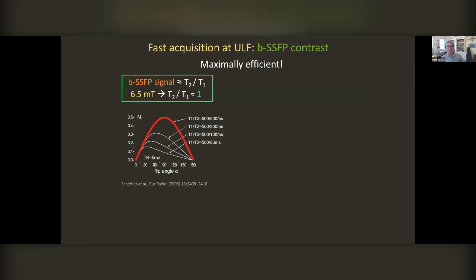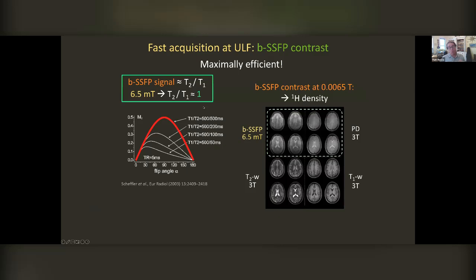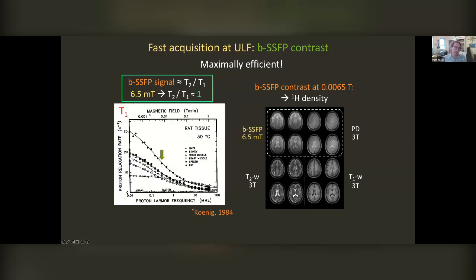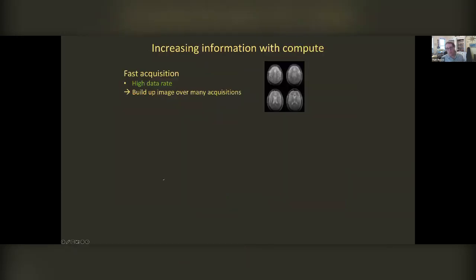Okay, so SSFP, it's maximally efficient at low field. The signal goes like T2 over T1. At our ultra low field, that ratio is unity. And so, we have very, very nice ways to acquire data. But of course, contrast is what all the neuroradiologists care about. And our images are kind of like proton density, which is really a shame, because as many of you know, I've plotted here T1 versus field strength. And there's a lot of interesting T1 dispersion in the range where we operate. And we have no way to tap that with this fast sequence.